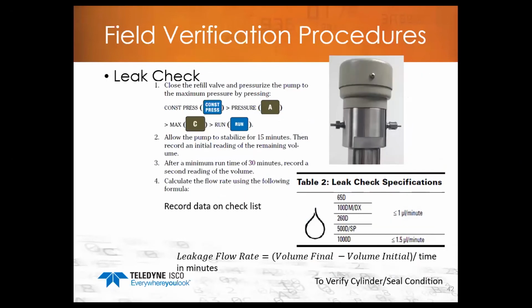Okay. The next thing you'll want to do then is a leak check of the pump. We always do our leak tests at the maximum operating pressure of the pump. When you run a leak check, you're going to have the pump dead-ended. You'll have both your inlet and outlet sides of the pump closed off. And we always do our leak tests with water.